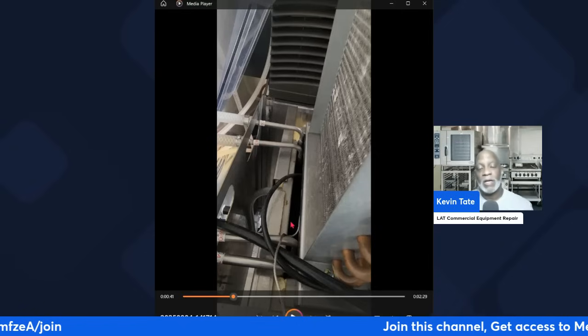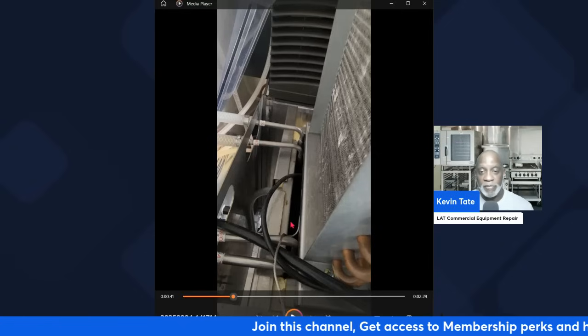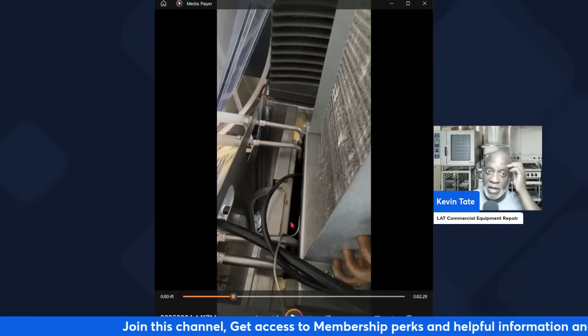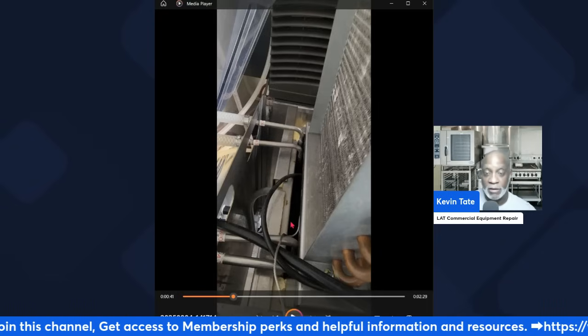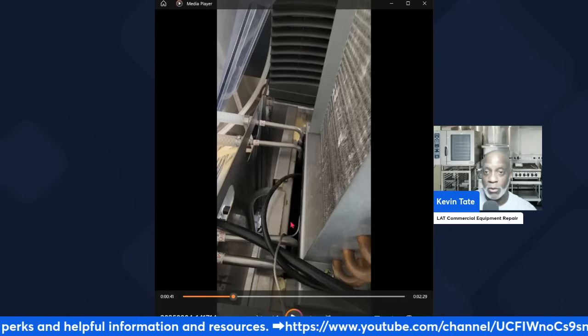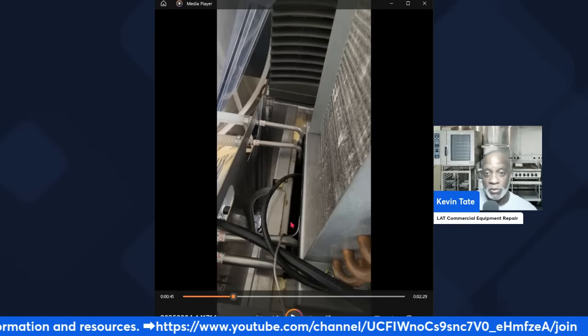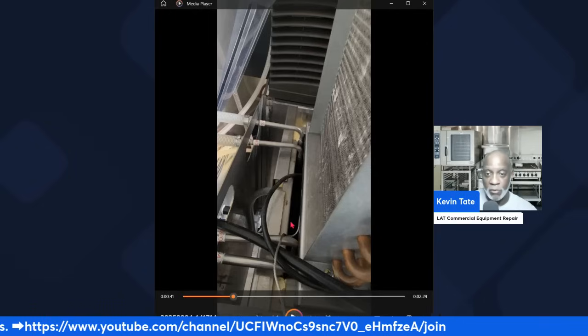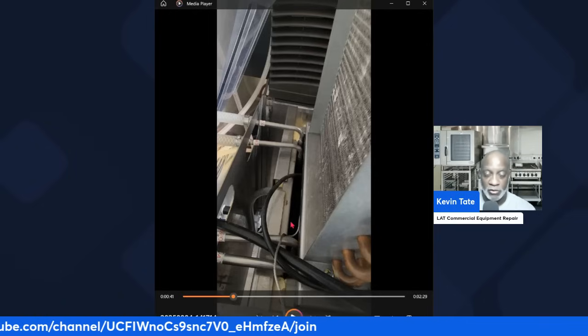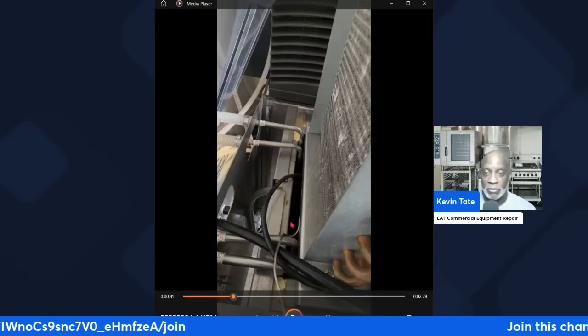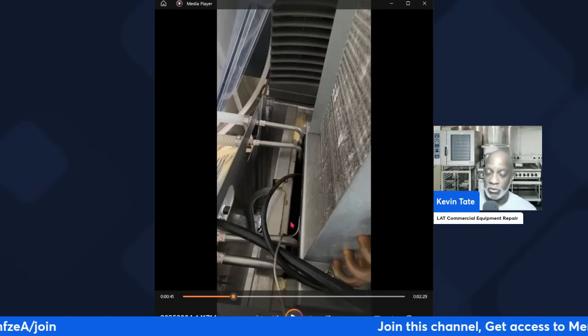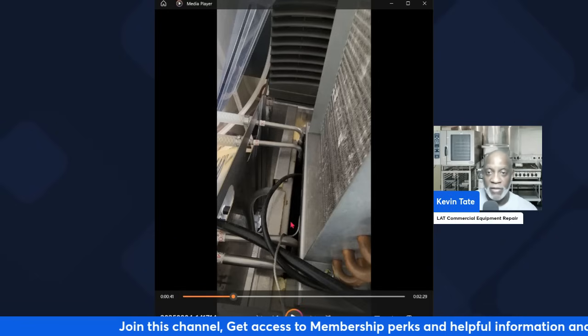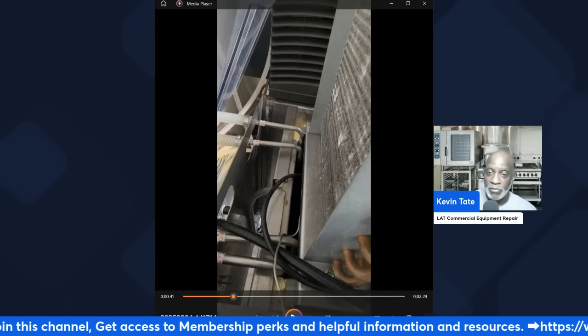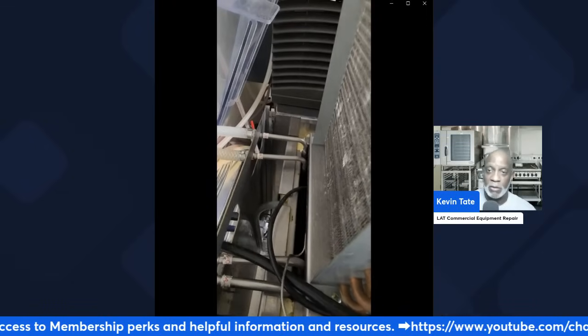So that's why they ran hot, both of them, because when I got on site it was very hot. The water pump was hot to the touch, and the compressor was hot as well. Of course it's going to run like that because there's no cooling going on. They're constantly running with no water in there to cool them down and release that heat. So that was the main thing going on there.